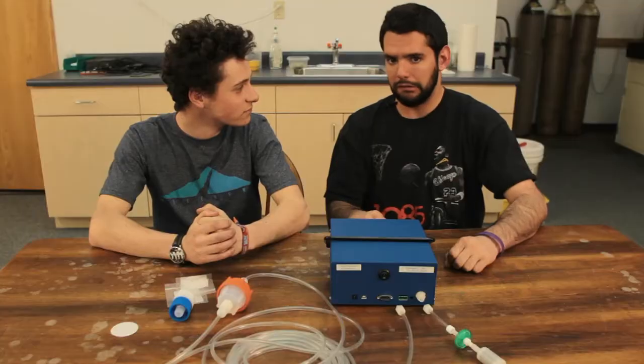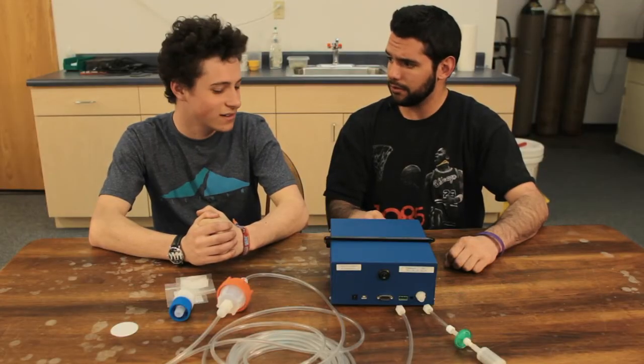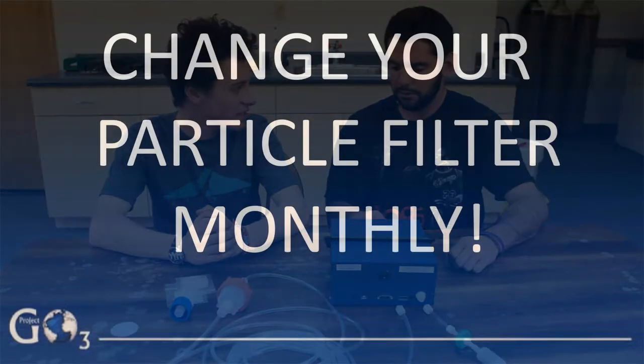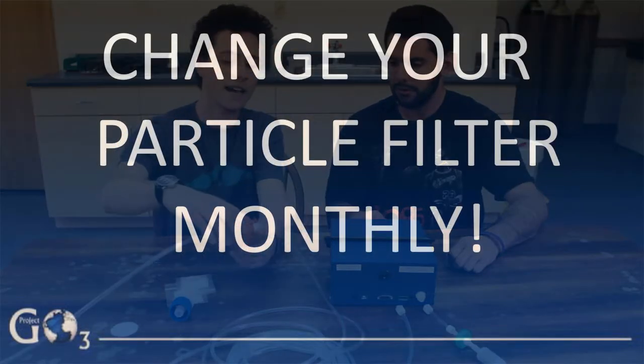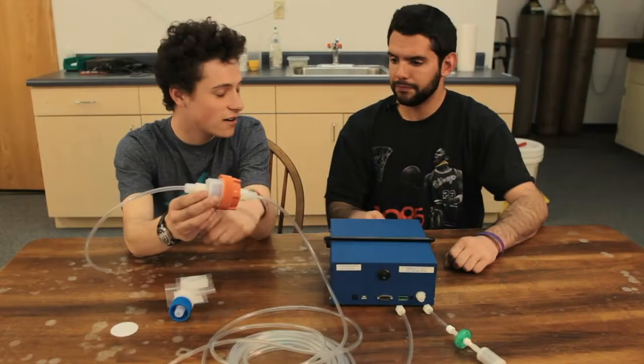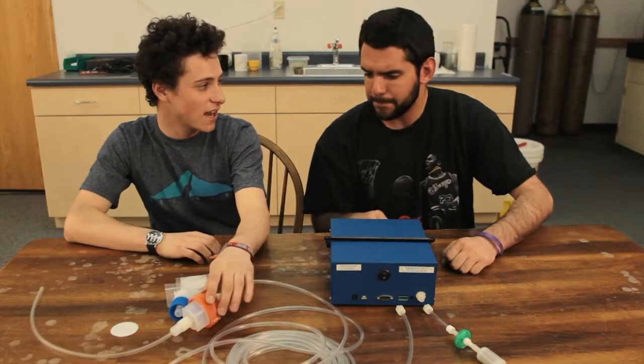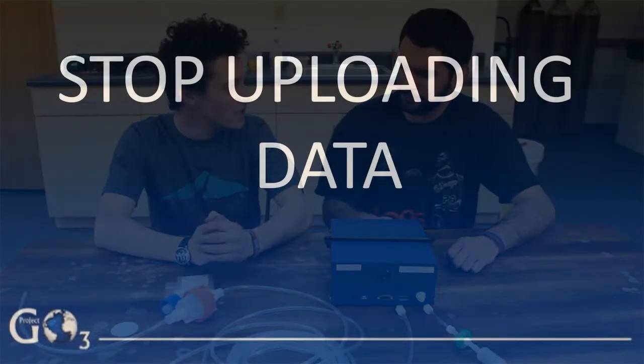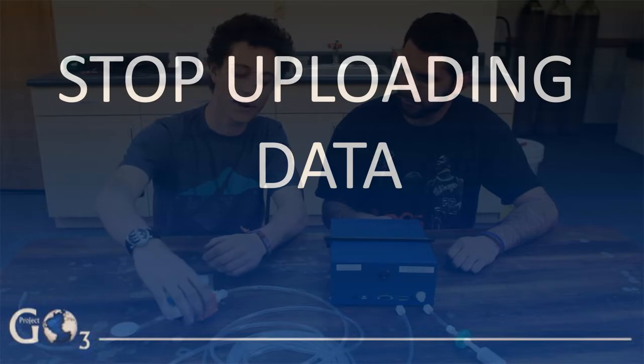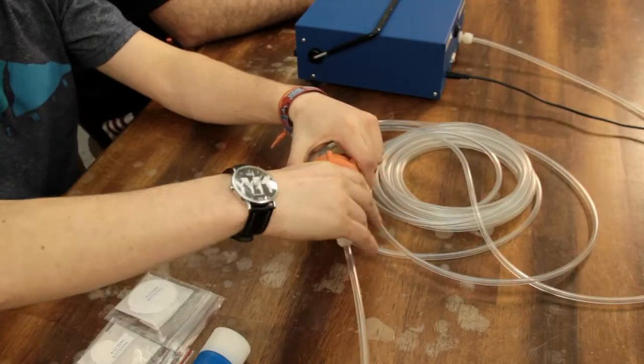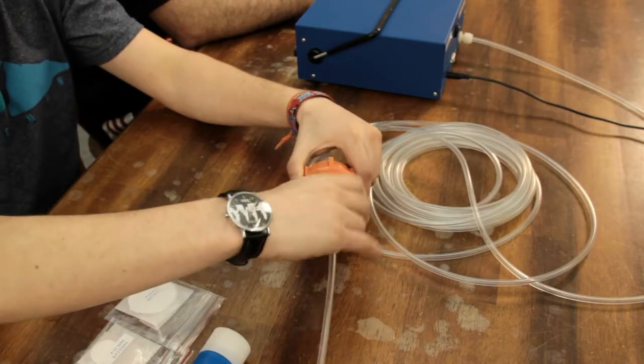Well, when's the last time you changed your particle filter? I don't even think I've ever changed a particle filter. Well, the particle filter needs to be changed monthly. It lies inside your housing. Before starting any maintenance, you're going to want to stop uploading data. Once you've stopped uploading data, you can start by unscrewing your housing, where you'll find your dirty particle filter.